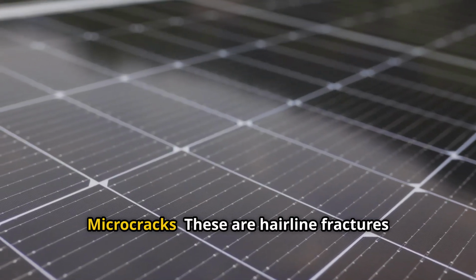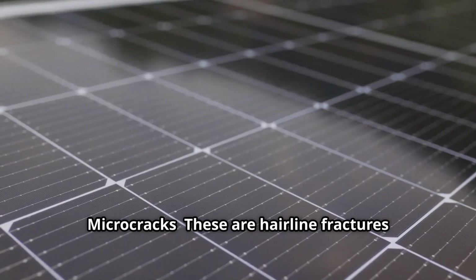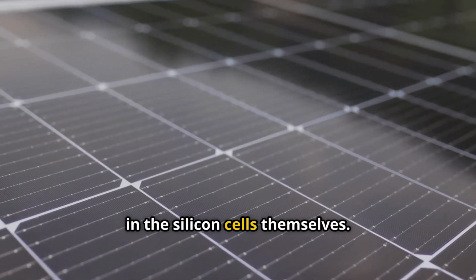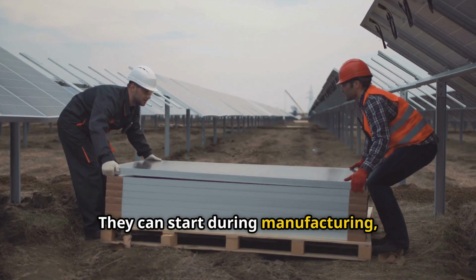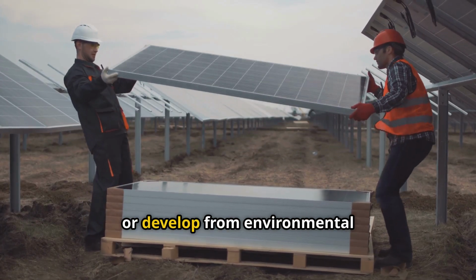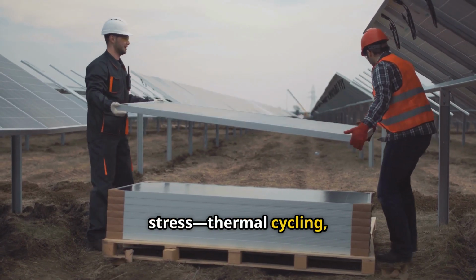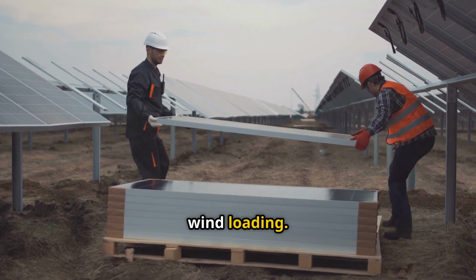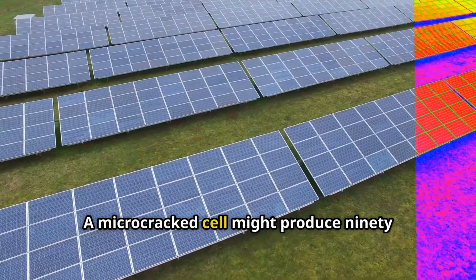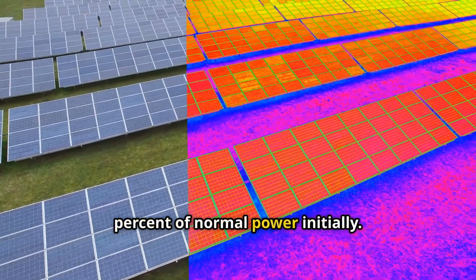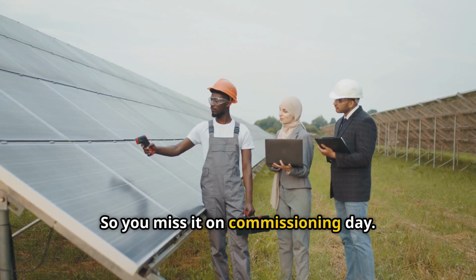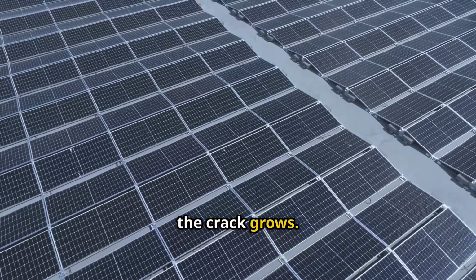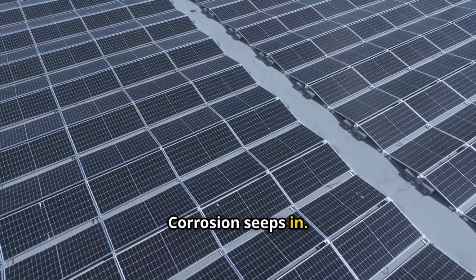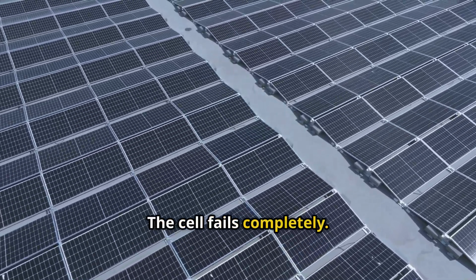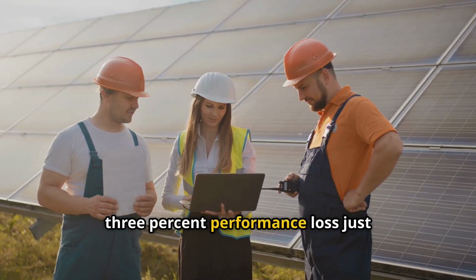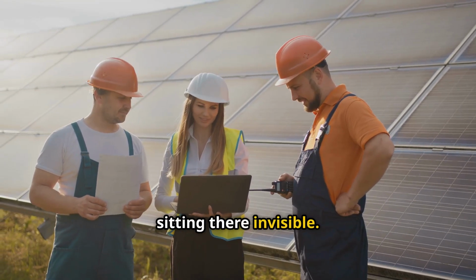Microcracks. These are hairline fractures in the silicon cells themselves. They can start during manufacturing, get worse during shipping, or develop from environmental stress: thermal cycling, humidity changes, wind loading. The tragedy: a micro-cracked cell might produce 90% of normal power initially, so you miss it on commissioning day. Then over time the crack grows. Corrosion seeps in, the cell fails completely. Microcrack damage costs around 2 to 3% performance loss just sitting there invisible.